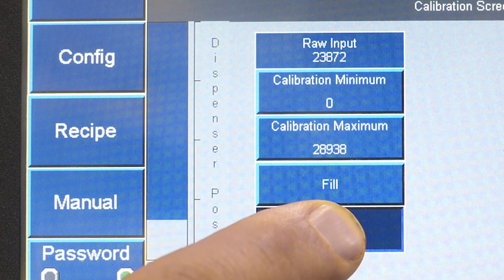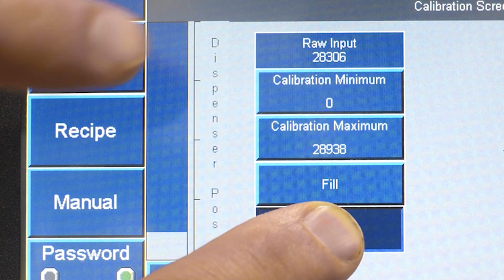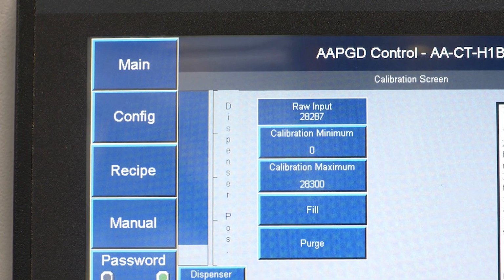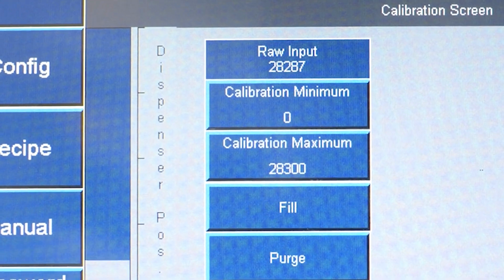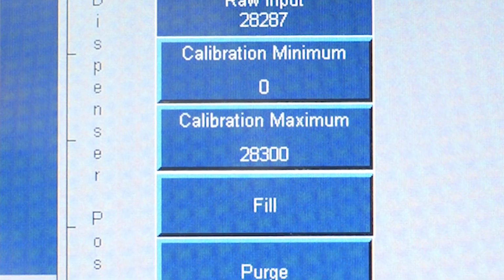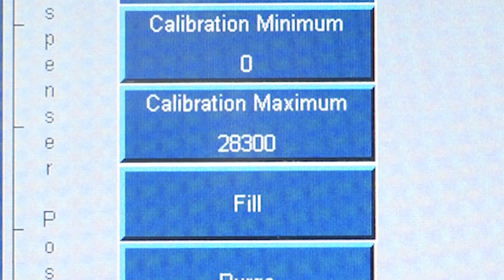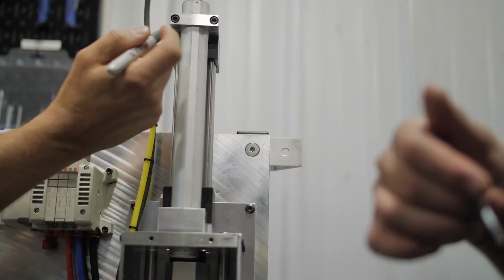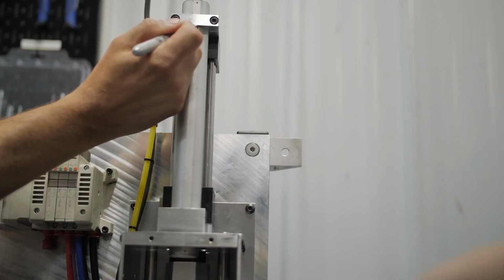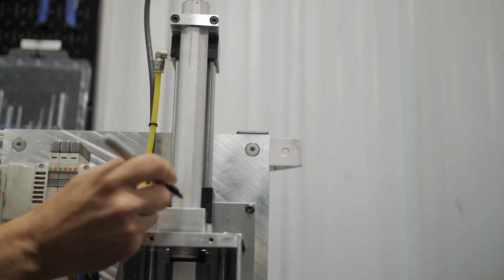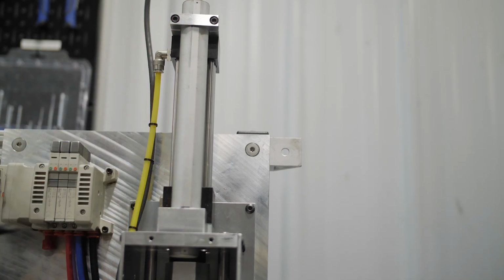After setting the linear position sensor to 0 or around 0 when holding the fill button, make sure that when you push the purge button, the raw input value is around the calibrated maximum. If you need to recalibrate the maximum to be similar with the raw input, hit the calibration maximum button and enter in the values you're getting in the raw input. It is recommended that you use a Sharpie to mark where the linear position sensor is, so that if it gets bumped, you know.